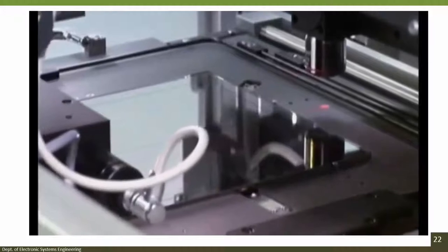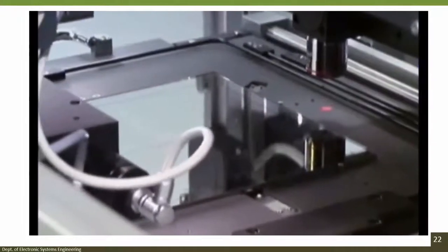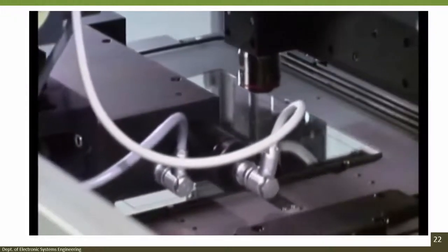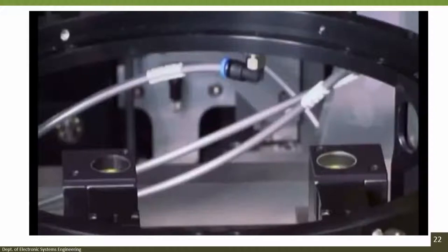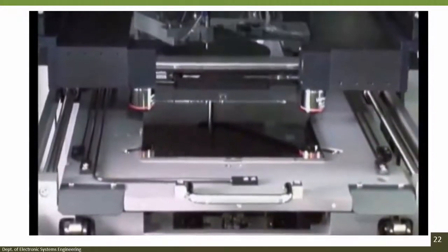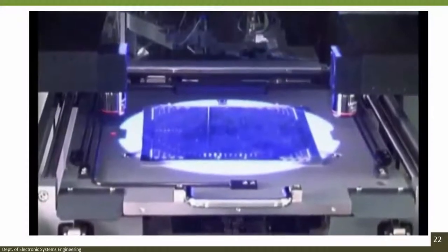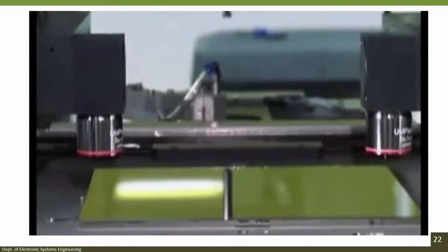The structures of the photomask are conveyed via shadow cast. The patented wafer leveling system from SUSS compensates for topographic variations and wedge errors, thus guaranteeing perfect alignment and exposure results. And the entire process is easy to monitor here on the touchscreen. Because of the MA200 Compact's newly designed microscope, during exposure, the mirror housing doesn't move forward. The microscopes only move sideways, thus reducing the vibrations of the alignment stage to a minimum, resulting in far greater accuracy. The optics of the MA200 Compact are optimized for thick resist processing.